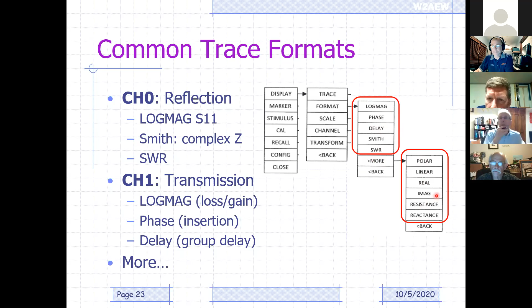Okay. So when you go to measure anything, you typically have to tell it over what frequency range you want to make this measurement. So that's what happens under the stimulus menu. Okay. And the stimulus menu allows you to define the frequency range one of 2 ways. You can set the start and stop frequency, where I want to start at 14 megahertz and stop at 14.3. Okay. Or you can set the center frequency and span.